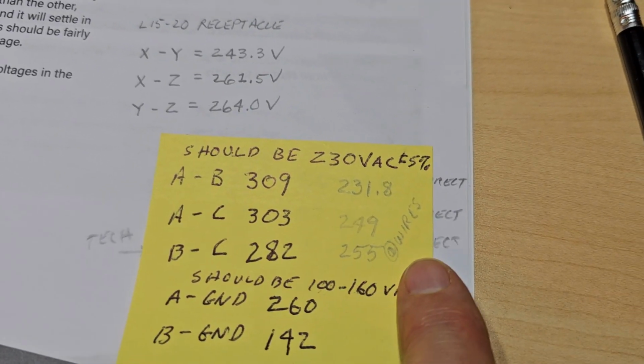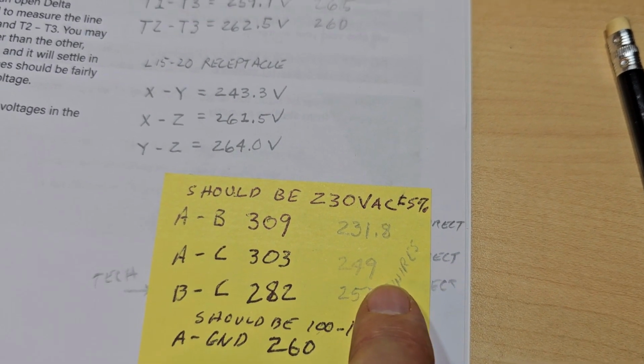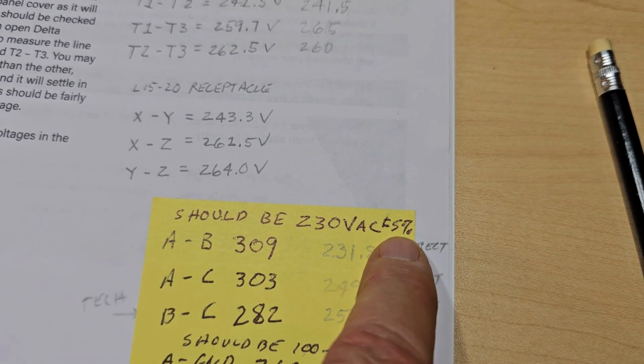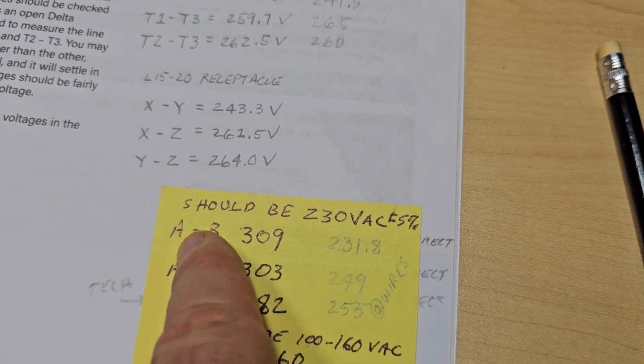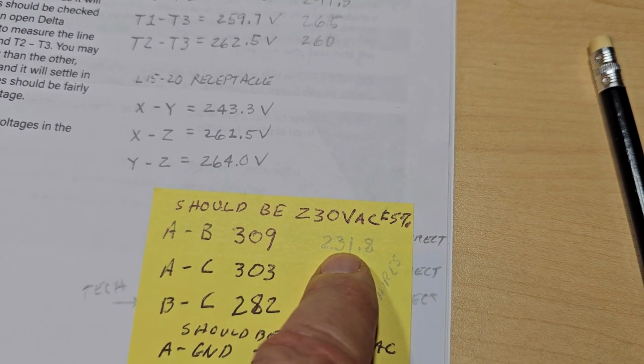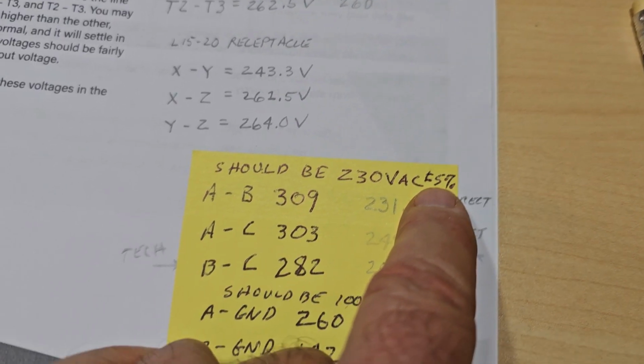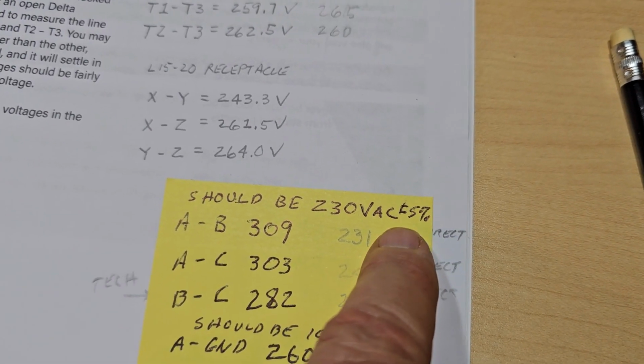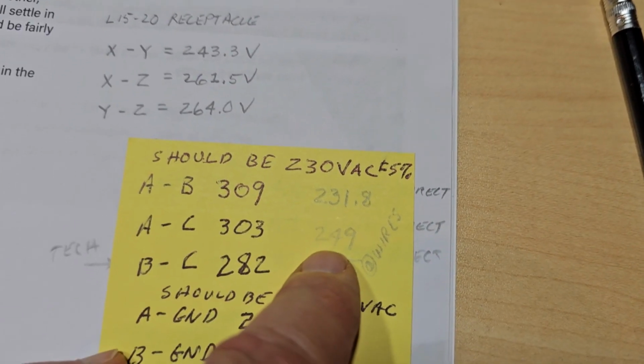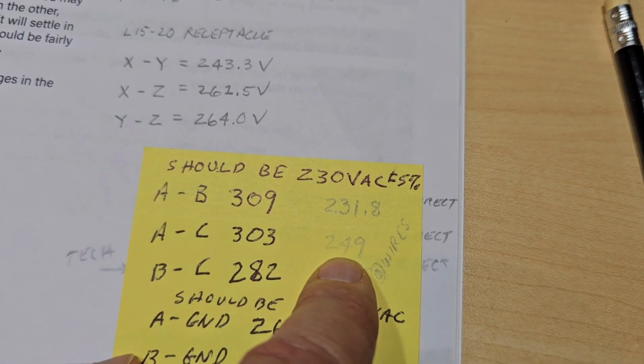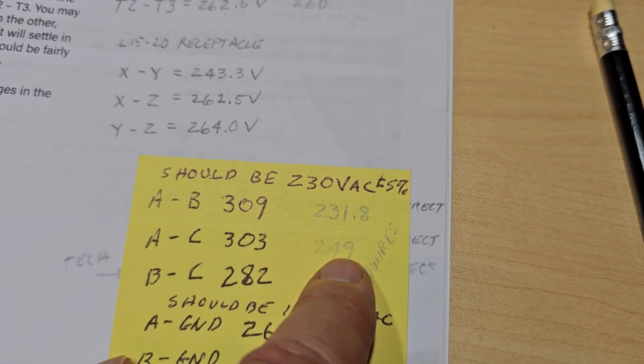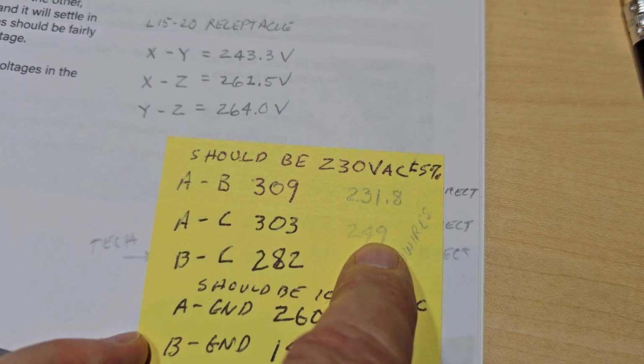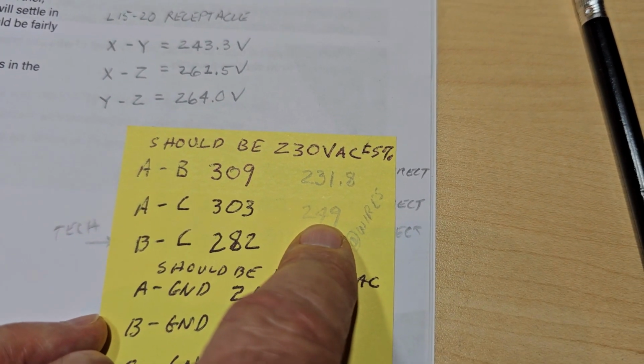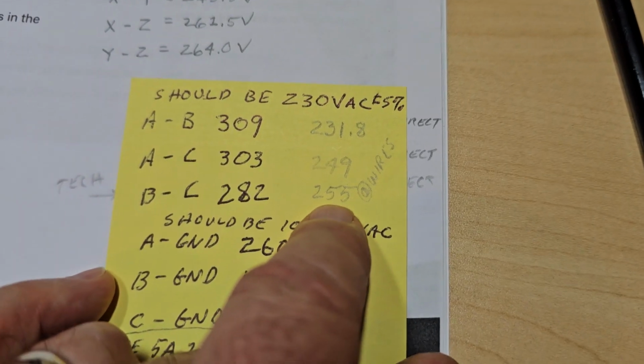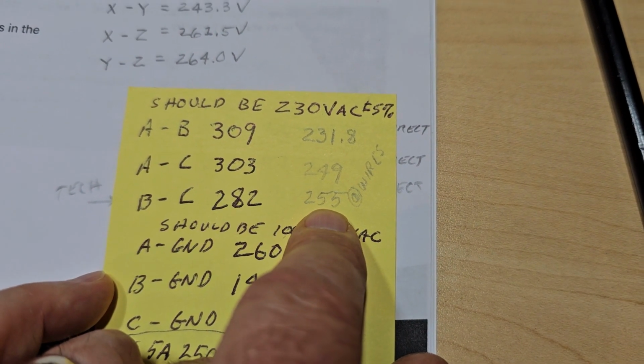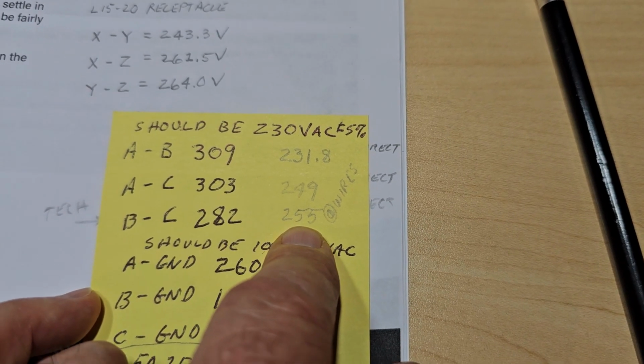Then what I did is I checked the wires. At the wires at the back of the machine, it should be 230 volts plus or minus 5%. From A to B, from black to red, I get 231.8. That's perfect. The maximum this can be is 241.8 with the 5%. So here I get 249 from the black to the white wire, which is no good. And you see that's too high. 249 is too high. It's out of the limit that the machine should have. And from the red wire to the white wire, I'm getting 255, which is even more.